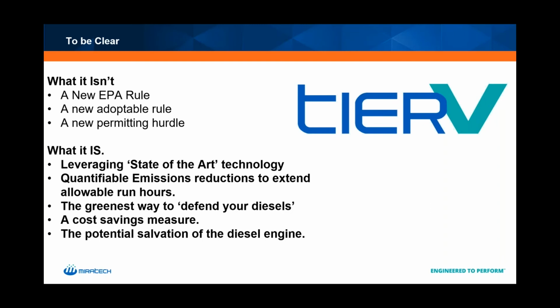It's quantifiable emissions reductions tied to extendable allowable run hours. What that means is, quite often when data centers build in phases, they'll put the first phase in with 50 to 100 run hours for those engines. With each additional phase, they cut those hours shorter and shorter to stay below a facility cap. That's fine, it's prudent, but at some point you cross over—when you're down to 2 hours of allowable testing time a year, you've sacrificed reliability of the whole system because you can't even test it.